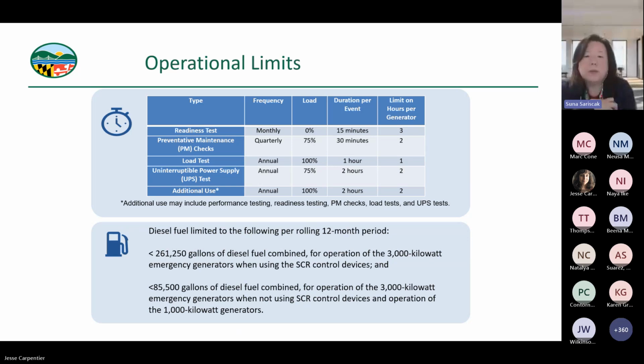And then Maryland required them to incorporate, at a minimum, what they believe would be a normal emergency operation, like the average number of power outages for the year. So that's the additional hours, and it also includes performance testing, readiness testing, or, if we wanted them to do stack testing, that's in that limit. And again, it's not a hard limit if they're still under 25 tons, but it's more of a guideline per generator. But because 10 hours per generator is exceptionally low as far as the proposed testing and maintenance schedule, and the NSPS requires them to operate and maintain their engines in accordance with manufacturer specifications, we did require the manufacturer to confirm that their proposed testing and maintenance schedule still met manufacturer guidelines.